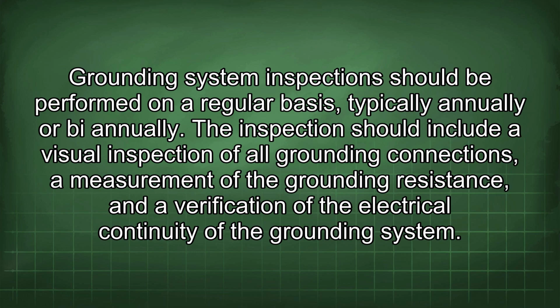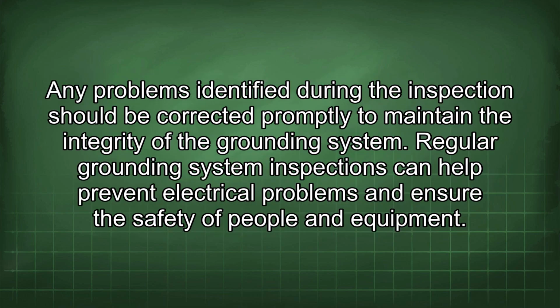The inspection should include a visual inspection of all grounding connections, a measurement of the grounding resistance, and a verification of the electrical continuity of the grounding system. Any problems identified during the inspection should be corrected promptly to maintain the integrity of the grounding system. Regular grounding system inspections can help prevent electrical problems and ensure the safety of people and equipment.